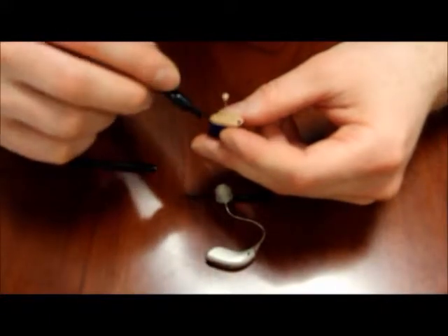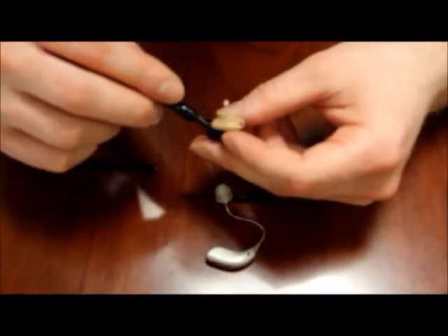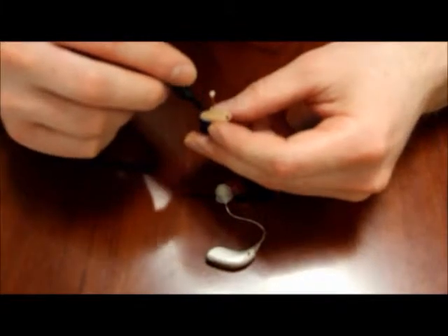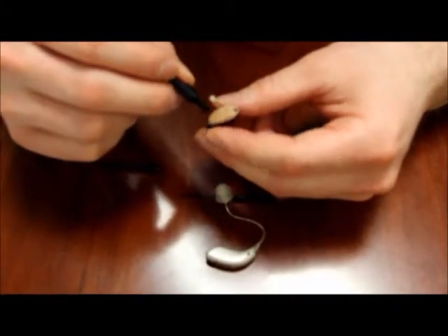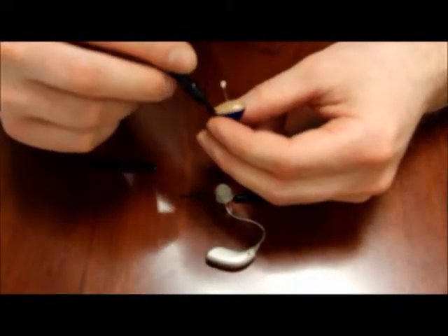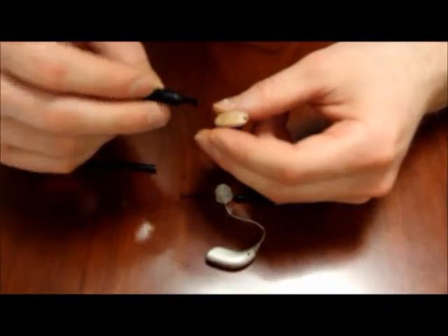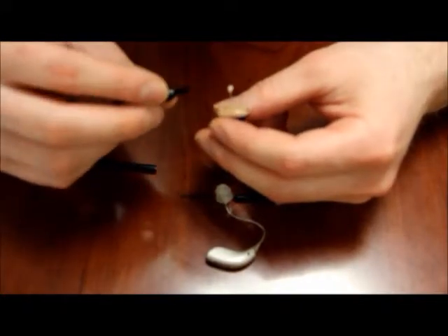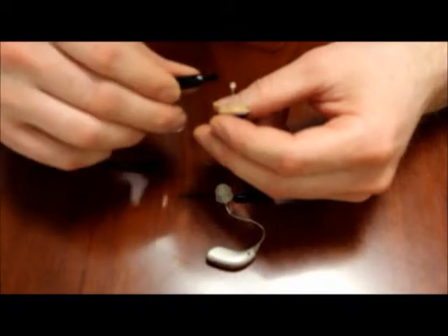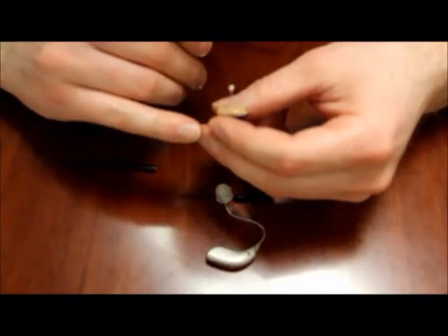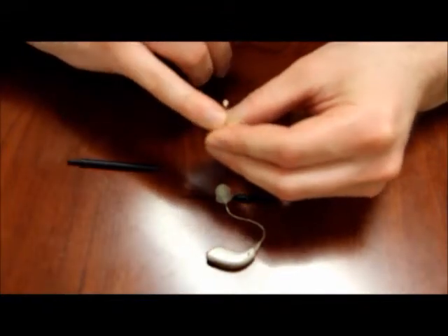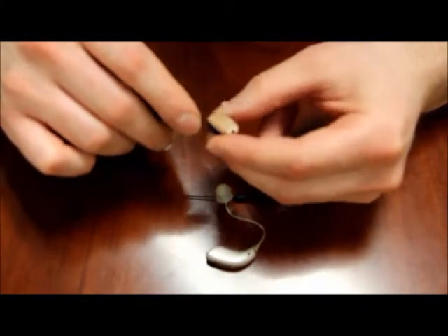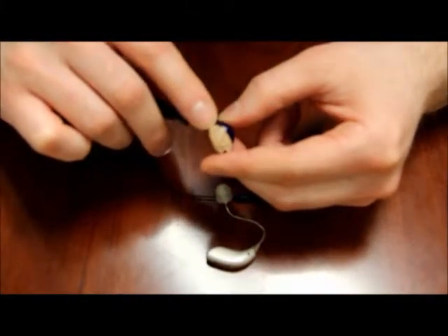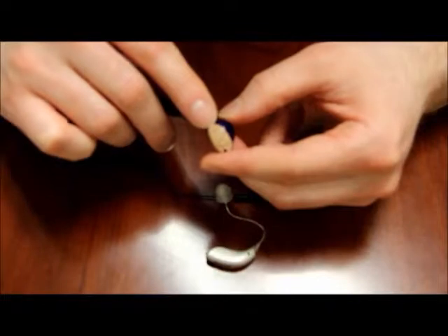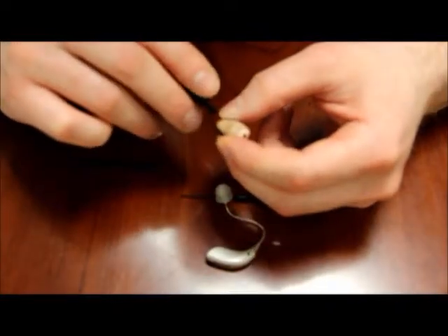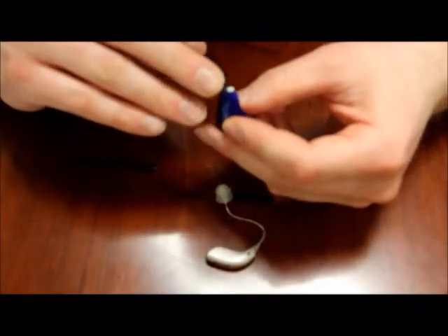With this particular one we have problems because the opening that lets the sound in is particularly small. So we have a lot of people that come in with this type of hearing aid who get them dirty, not even by knowing it, just by using it daily. They get a little bit of dead skin or earwax on their hand, and when they push the hearing aid in, they're also pushing in wax into this opening right here that's going to be tough for you to see. So you want to keep that clean, as well as the other end.